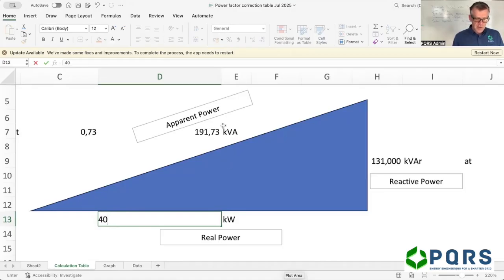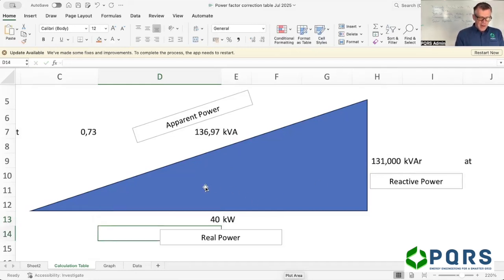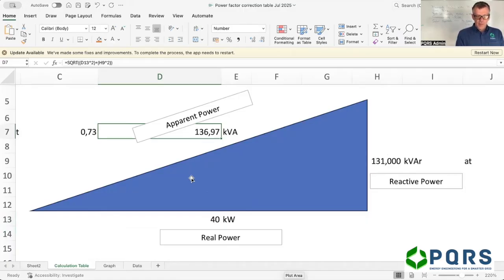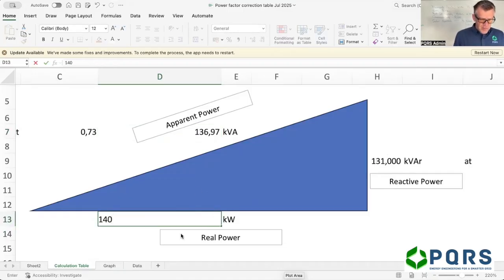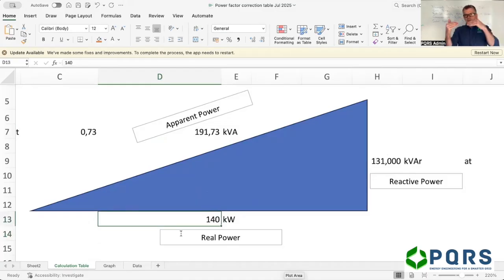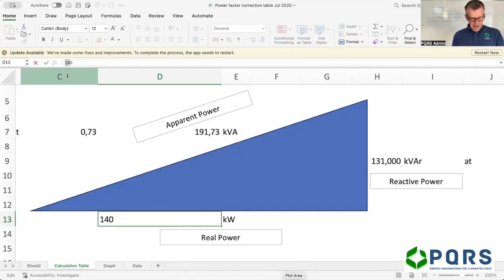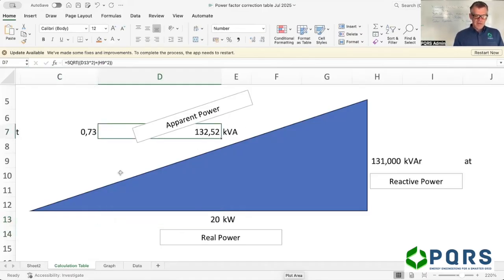Have a look at what happens to your kVA, because your kVAR, your reactive power component, is going to stay the same. It drops your kVA down to 136, which I don't think is significant. It's substantial, but it's not. From 190, look at the comparison between the kilowatts being drawn and the demand. So you go down from 140 to, let's make it, 120 kilowatts being provided by the solar system. So you're only drawing 20 kilowatts from the grid. Look at your demand. Your demand's still sitting at 132 kVA, even though you're only drawing 20 kilowatts from the grid. And that is because your reactive power component stays the same.